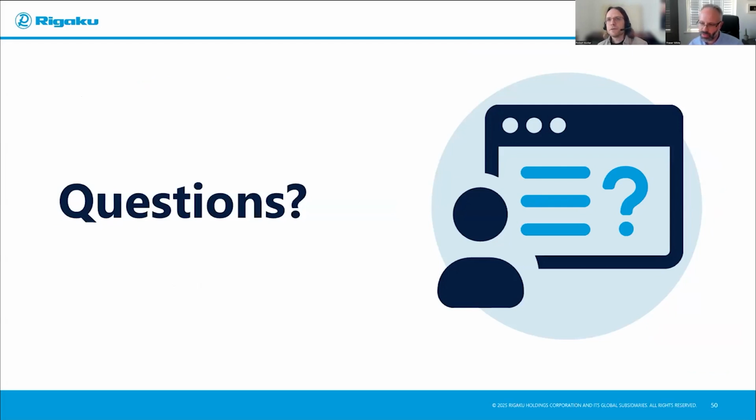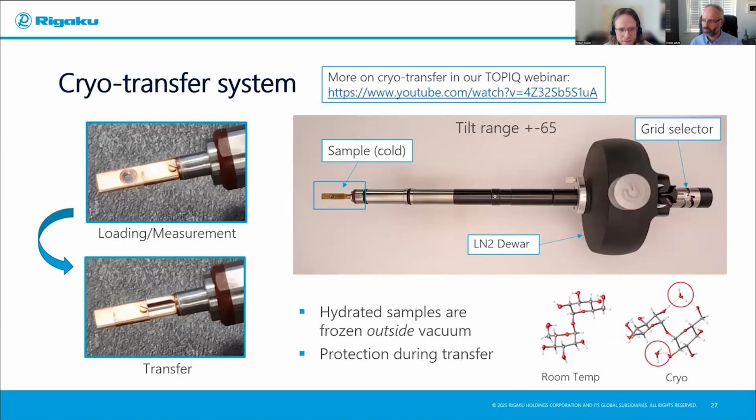The cryo transfer holder, you mean for air-sensitive materials? Well, if you can come up with a workflow where you would transfer this sample into the holder inside a glove box, then you can make a reasonably air-free transfer, because this environment here will be filled with dry nitrogen.